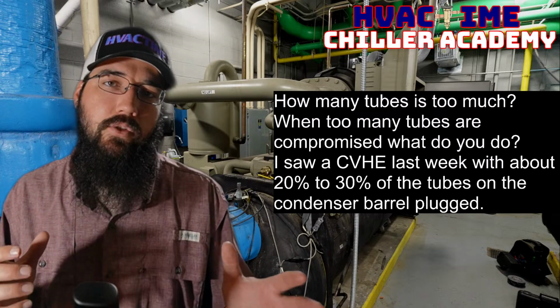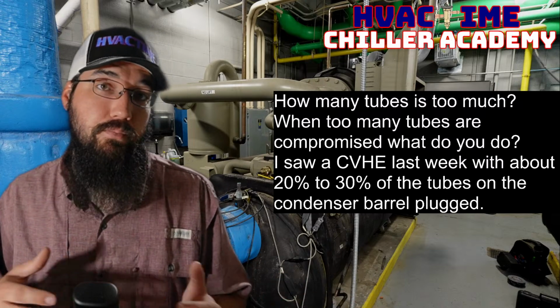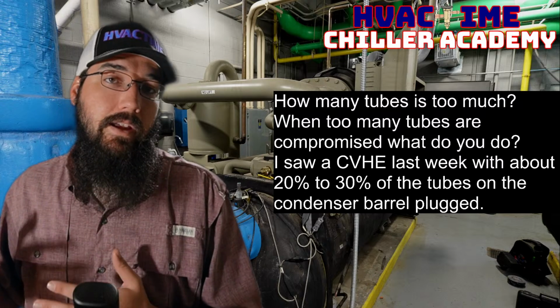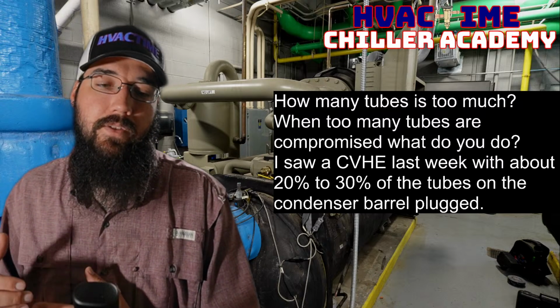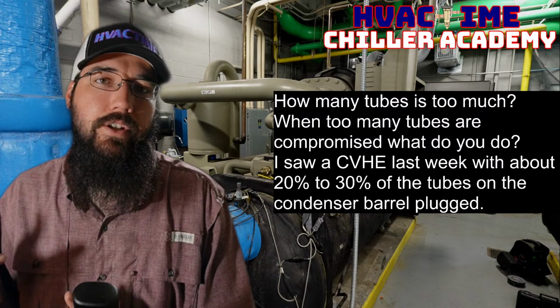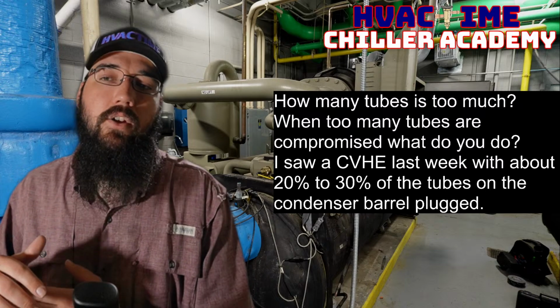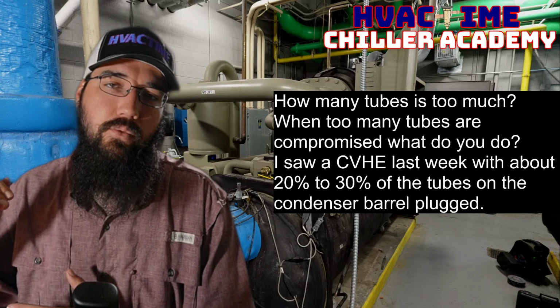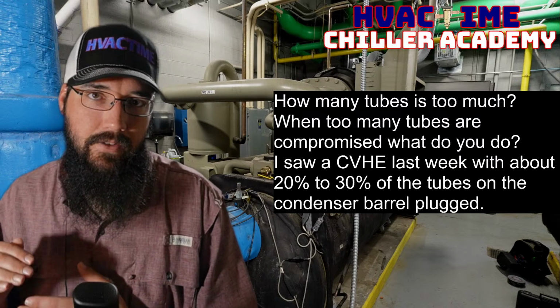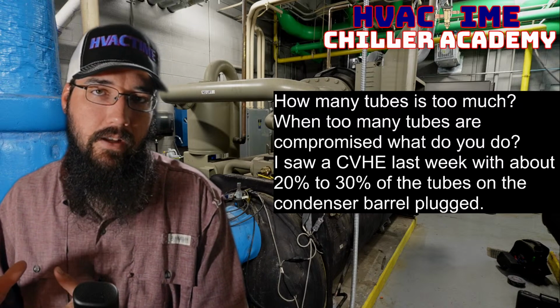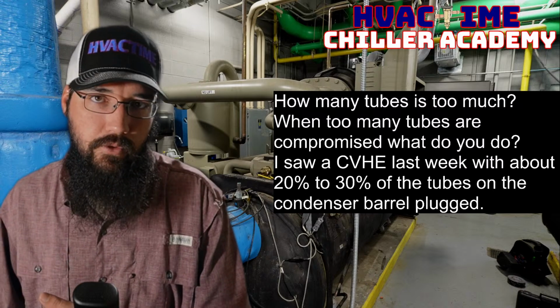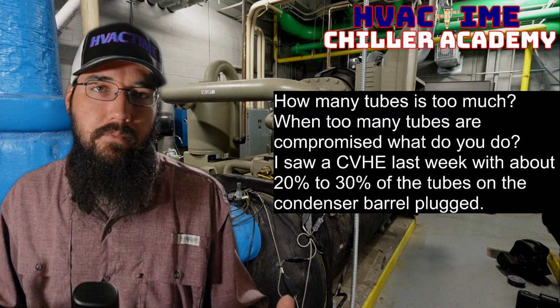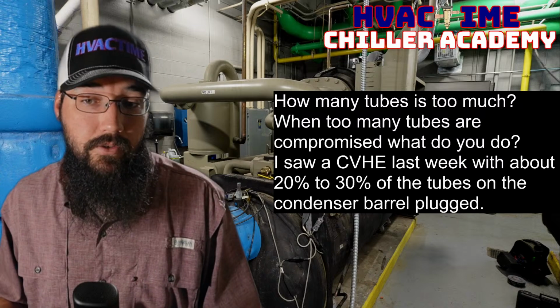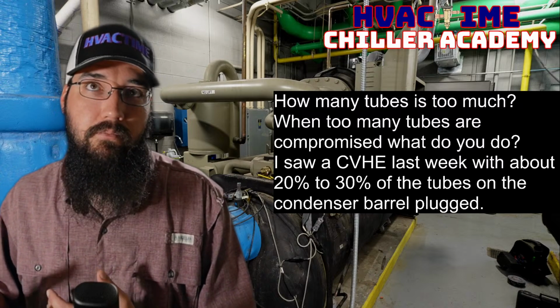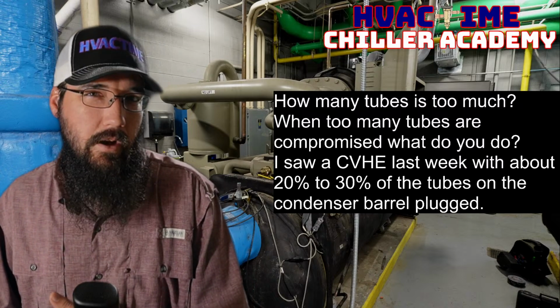Okay, so those are some things, or that is what my training is on that breakover point. And so typically what I've done is I'll just push that machine up to that limit. And when I get to the point where the condition is just too severe, right? What I mean by condition is we're having trouble maintaining stable operation because we just can't exchange enough heat through those tubes. It's time to consider either doing a retube, which would be a pretty common next step, right?